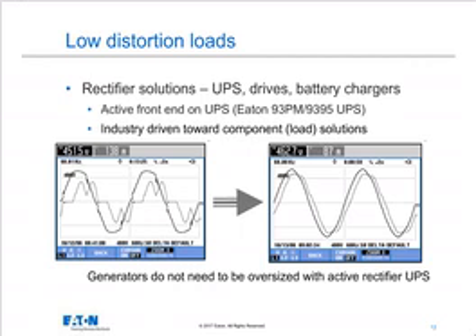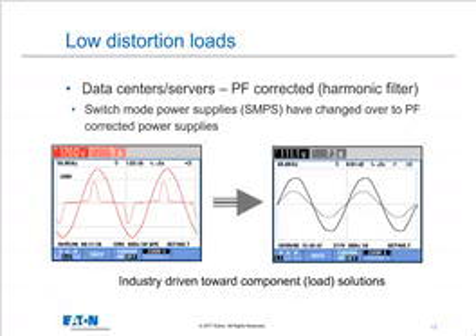Now today's modern UPSs, like the 9395 and 93 PM, use an active rectifier. So it's almost like having an active filter built into the front end and basically taking a 6 or 12 pulse front end and making it look nice and clean. The other thing I don't show here, but you could also do, and we do, is put the power factor right on unity, so we can control the power factor in the harmonics. So the industry is driven towards these solutions, and just so happens with the UPS, it's also a very economical way to do it.